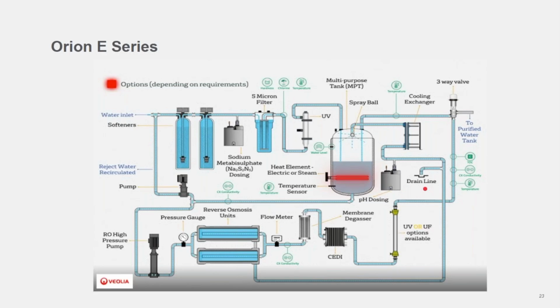The other thing we do with the current unit, which is the Mark III, is that traditionally when we were in recycle, we would run at full flow. So if this was a 4 meter cubed an hour unit, we'd be running at 4 meter cubed an hour during that 8-hour recycle period. What we do now is drop the flow down to approximately 2 meter cubed an hour using a variable speed drive on the high pressure pump. And this also saves electrical energy. So there's 2 areas there where we try to tick a few boxes on the sustainability front: A is in the water footprint and B is on electrical energy. So that's the E series.